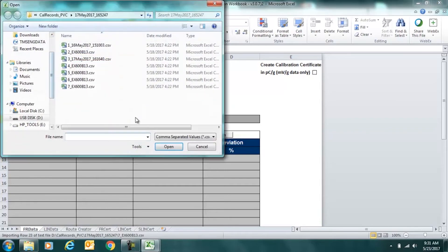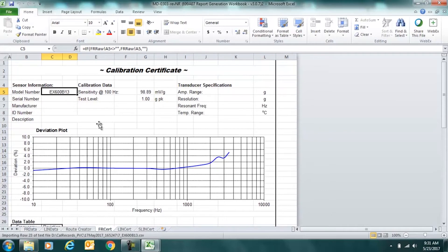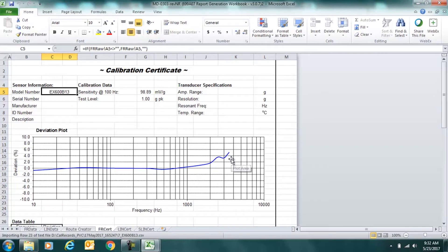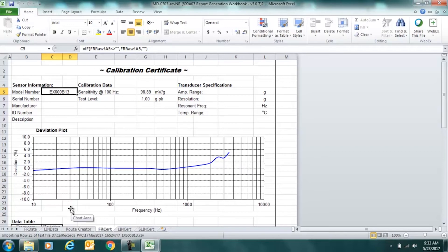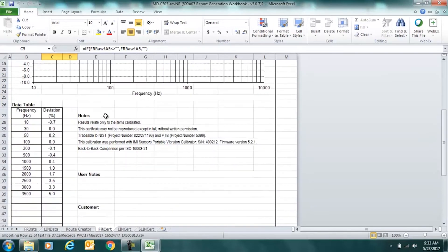From there, we import data from file, click on the calibration record that we wish to create and our raw data comes in and now we can hit view certificate. You can see that your eyes first go to the deviation plot. Our percent deviation from sensitivity at reference is calculated here and displayed in this graphical format. If you've ever looked at a calibration certificate from PCB Piezotronics or another vendor, this should look familiar for an accelerometer and the frequency is displayed on the bottom axis. Our model number automatically comes in. The sensitivity at 100 hertz is shown here and the test level of 1g is also shown.